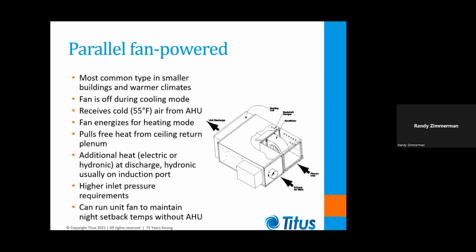During the cooling mode, the fan is off, and the primary air valve is simply conditioning the space just like a single duct VAV box. Then as you have less cooling demand in the space, the primary damper closes down to a minimum ventilation flow rate just to provide ventilation to the room. And if the room temperature continues to drop, then the fan kicks on to pull that warm return air from the ceiling plenum and move it out to the room.